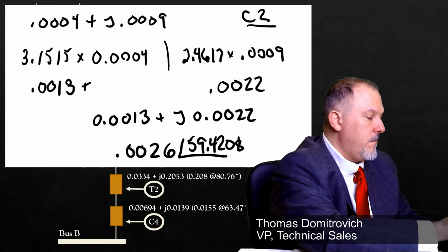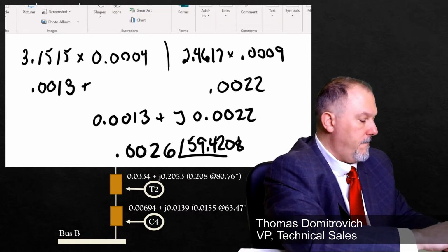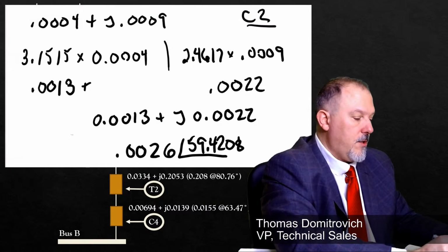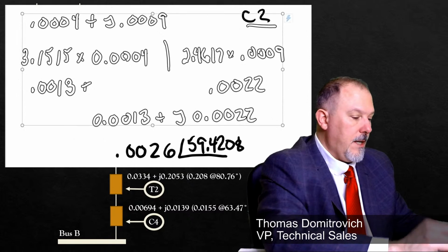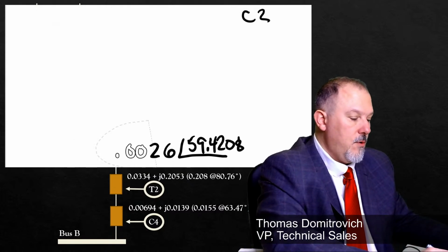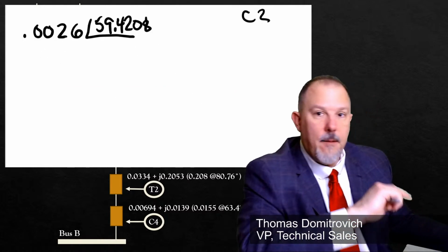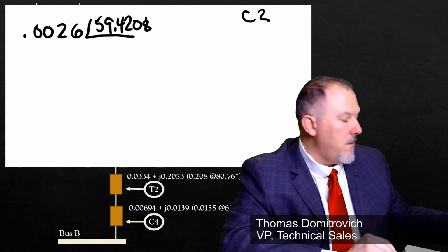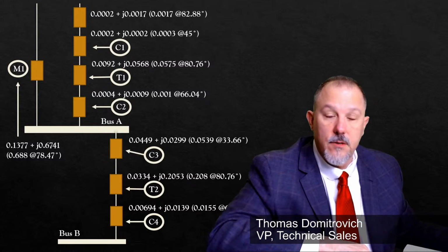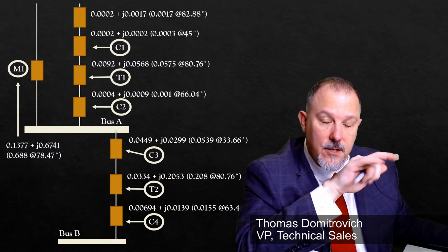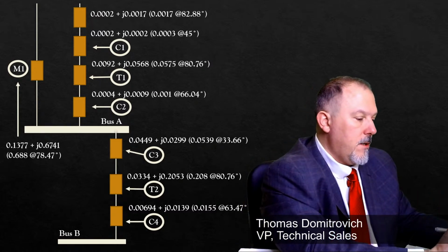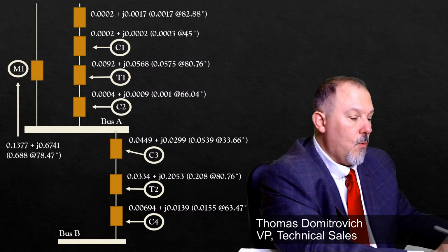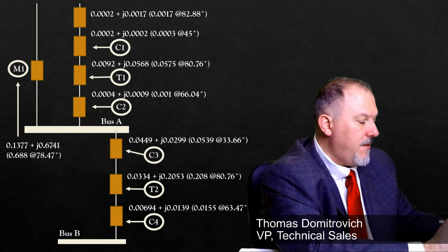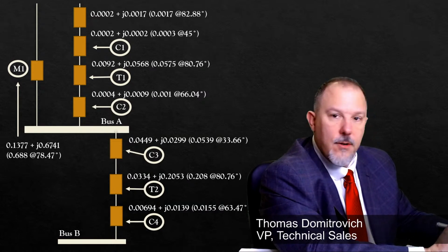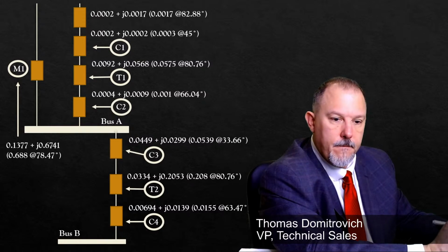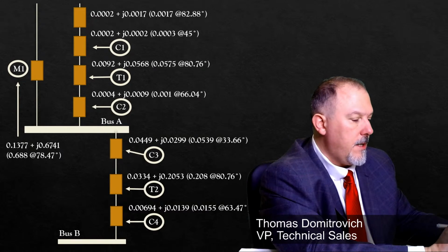Now, what do I have to do? Insert new duplicate. I am going to delete all of this. I am going to move this up. Now, my zero sequence diagram is going to include that. That's the conductor we just calculated. This is conductor 2. Transformer 1 is 0.0575 at an angle of 80.76 degrees. Okay.